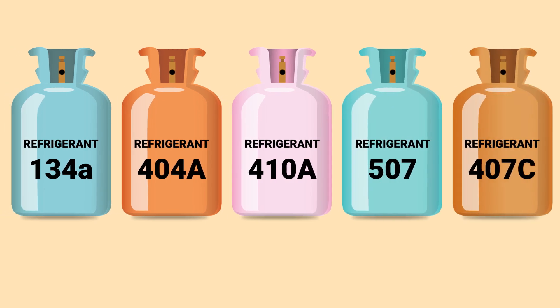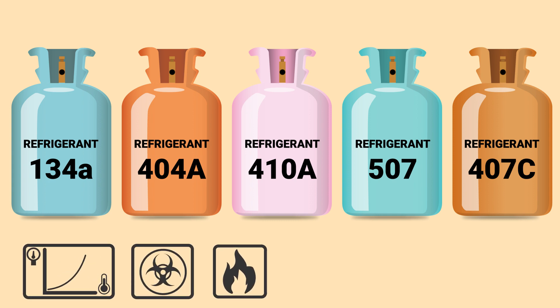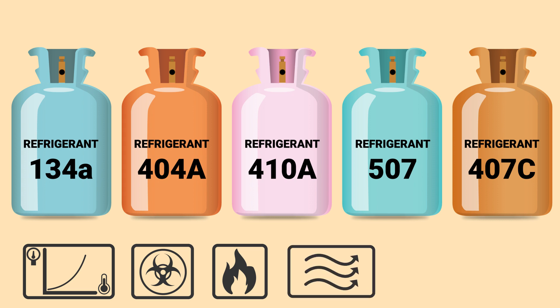Refrigerants are the lifeblood of a system and they have been for a long time. To have a refrigeration system you need something to act as a refrigerant, and refrigerants are chosen based on a lot of different reasons: their pressure-temperature curve, whether they're toxic or not, whether they're flammable or not, and of course how efficient they are — in other words, how many BTUs per pound does R134A absorb changing from a liquid to a vapor versus R404 or R410. This adds up to the overall efficiency of the system.